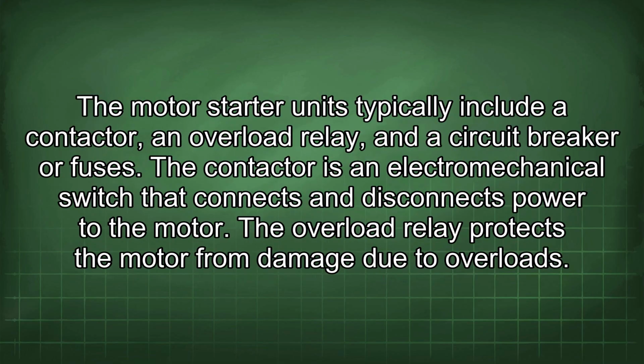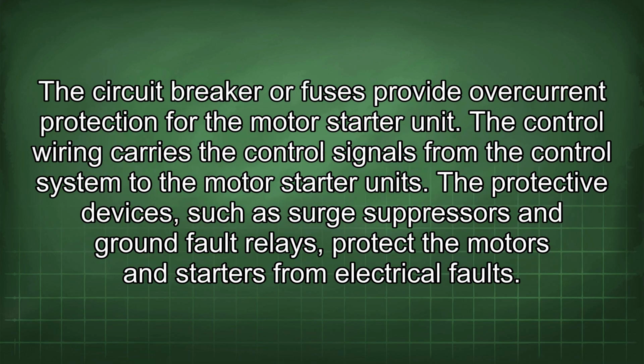The motor starter units typically include a contactor, an overload relay, and a circuit breaker or fuses. The contactor is an electromechanical switch that connects and disconnects power to the motor. The overload relay protects the motor from damage due to overloads. The circuit breaker or fuses provide overcurrent protection for the motor starter unit. The control wiring carries the control signals from the control system to the motor starter units. The protective devices, such as surge suppressors and ground fault relays, protect the motors and starters from electrical faults.